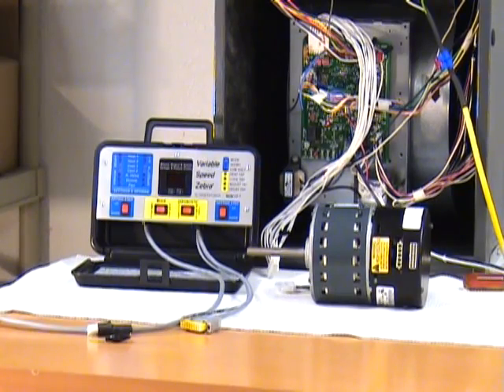When you examine a variable speed system for the first time, it looks complicated, and indeed it is. Besides the 5 lines that go to the power section of the motor, the 16 pins that connect up to the signal section of the motor have, besides hot and common, many wires that run at half wave. They're rectified AC, so their voltages are hard to measure properly. And some of those wires, you can only tell what the signals are saying with an oscilloscope. A general voltmeter won't give you any good indication at all. The homeowner just tells you to fix it, please, and you might not be sure where to start. So we've made a tool that'll help you make an accurate diagnosis of the problem the first time.